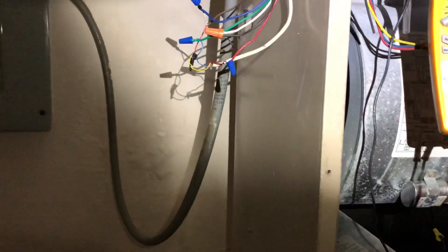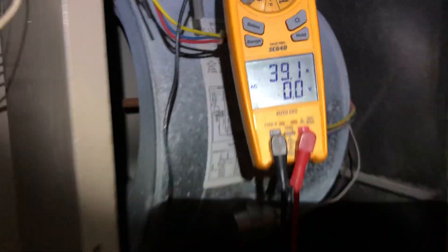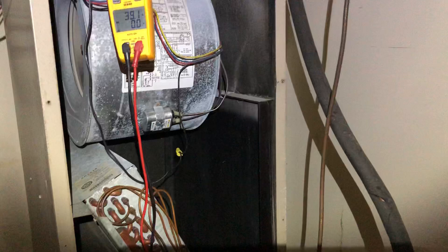So I turned the thermostat on heat. It's been running now for about 10 minutes, and I'm getting a good amp draw — 39 amps on 208 volts — so I'm good to go with that.